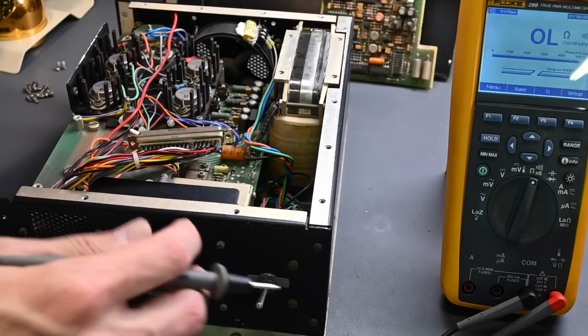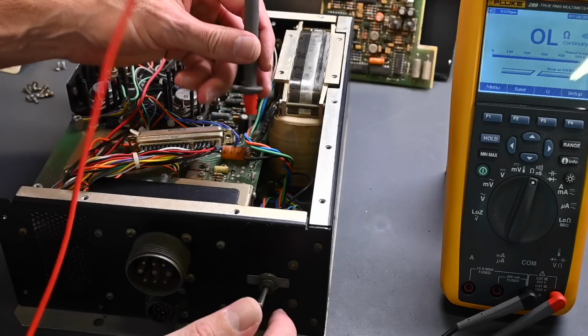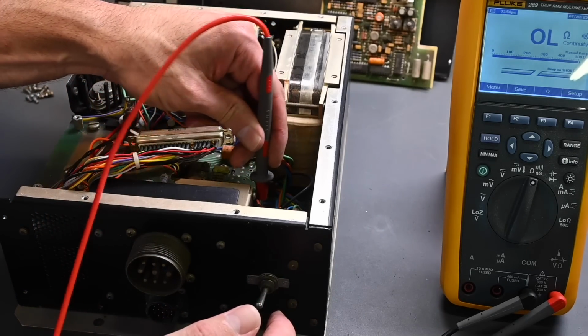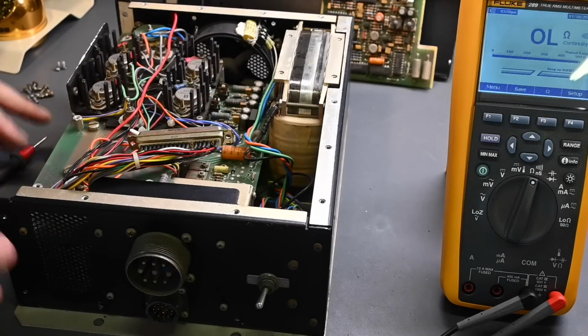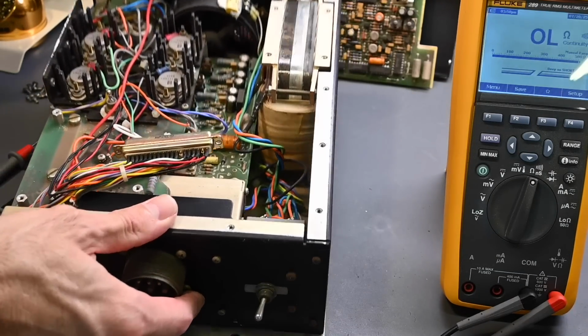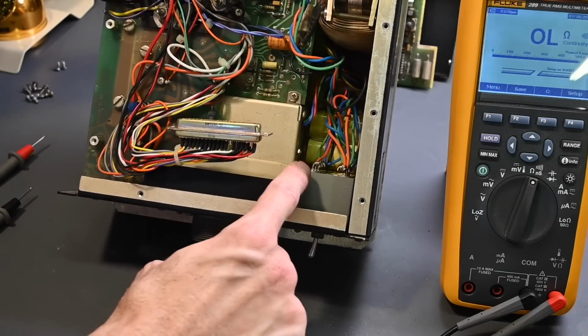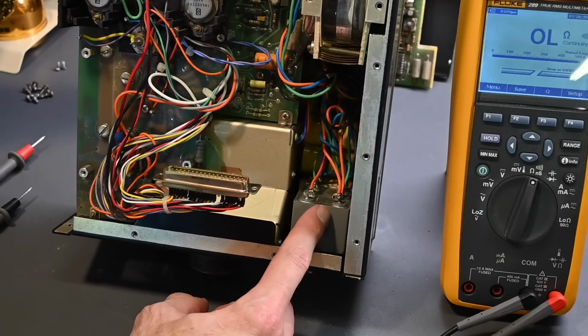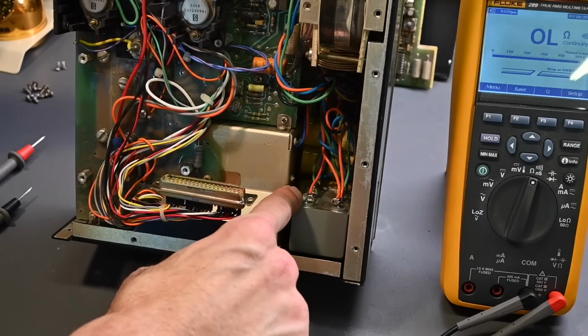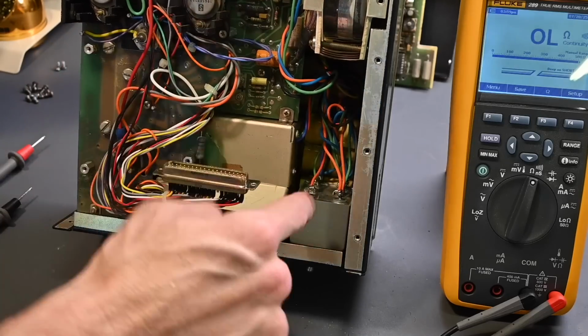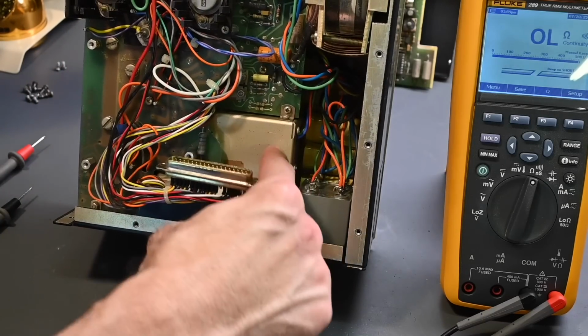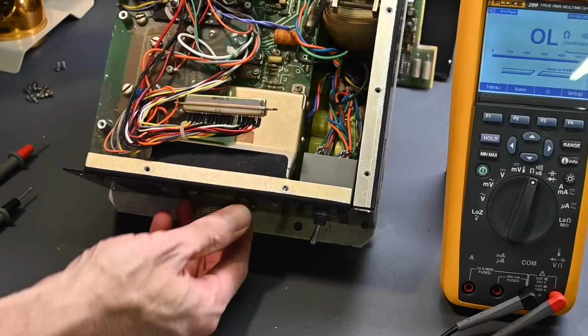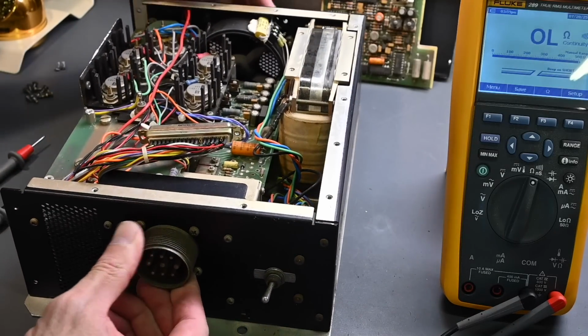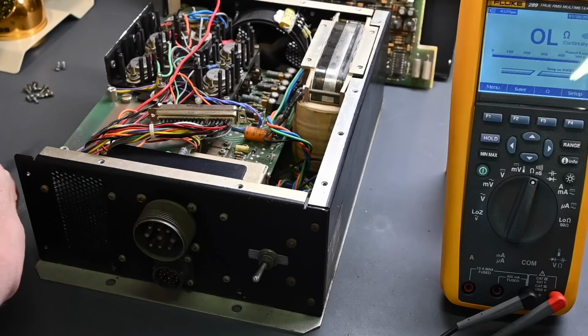What I will do is just go to this one side. It looks like right here, this wiring down inside, tip this up again right here. You can see on the back side of the circuit breaker, this wiring right here, again color-coded with the same colors that go to the transformer. This wiring is looping around and going into the shield, or this box that's right behind this circular connector. So I'll just probe on that side of the circuit breaker.